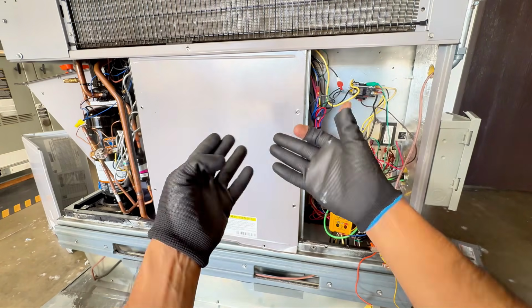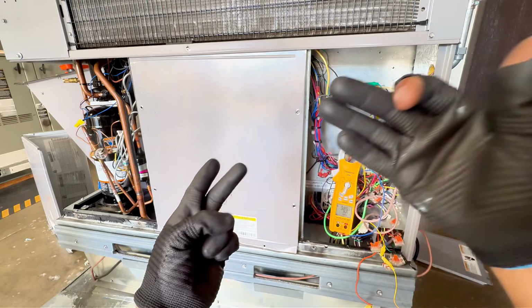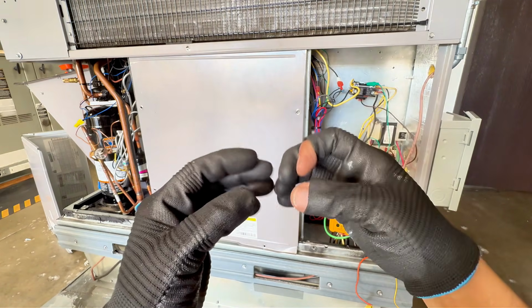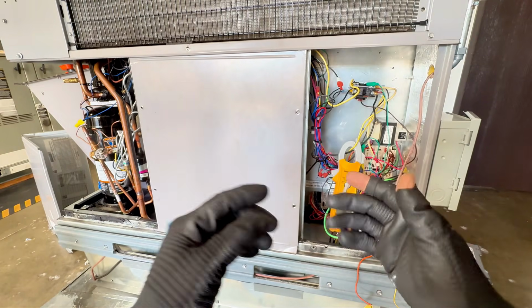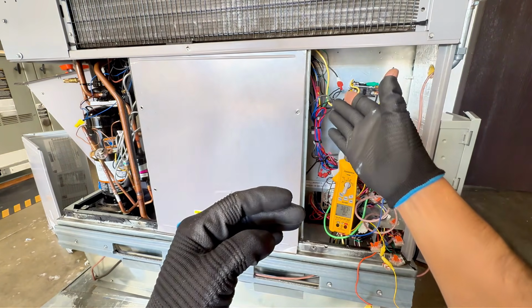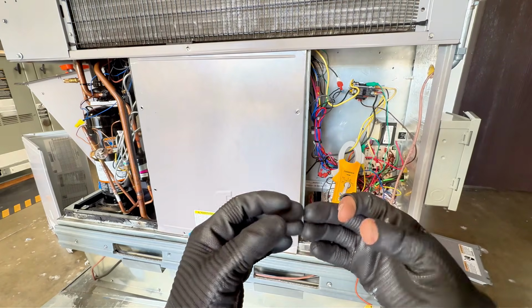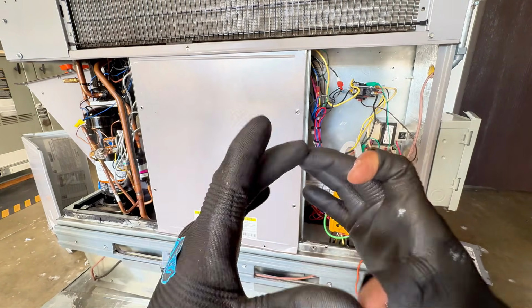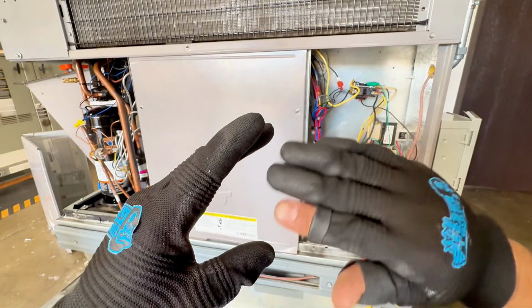With systems with an ECM, change out the filters, check the supply vents are open. This is a big one, making sure the return ducts are properly sized for the unit. The moment that you create a restriction, you can see right here the current went up. Current is heat, and a lot of the ECM motors, when you look at the module, instead of it being green, it's kind of yellowish because it's pulling more current.